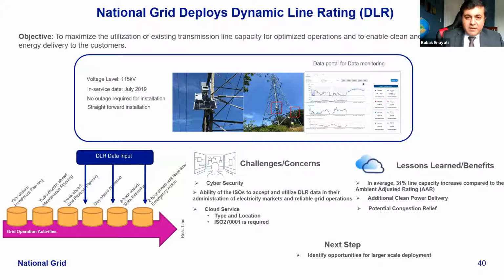The technology we worked with is Line Vision, installed on a 115 kV line. It was commissioned in July of 2019. The installation is very straightforward, no outages needed. Sensors are installed on the tower, and with LiDAR it looks at the line sag and all the conditions that would impact the dynamic rating of that line.